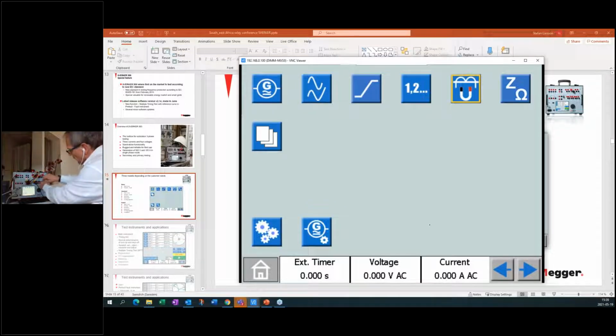Then I remove these jumpers I have here. It looks like this. Very easy to connect on the Sverker 900. So I remove the cables for the CT magnetization test. I don't need them anymore. Okay. So I will connect the power, which I would like to have to the protection, like this. Up here in the top, I have the connections for the three phases of current, so phase 1, 2, 3, and the neutral coming back from the protection. And on the left side, I have the binary input with the trip from the protection.